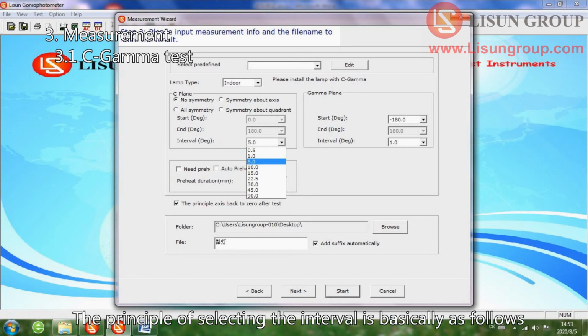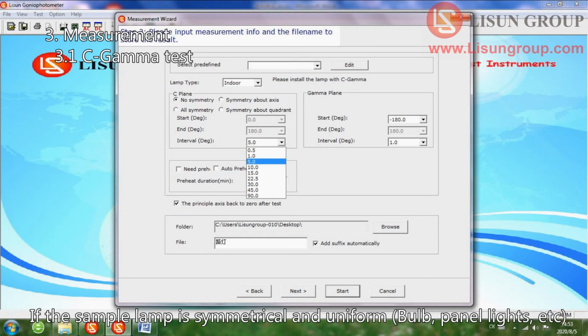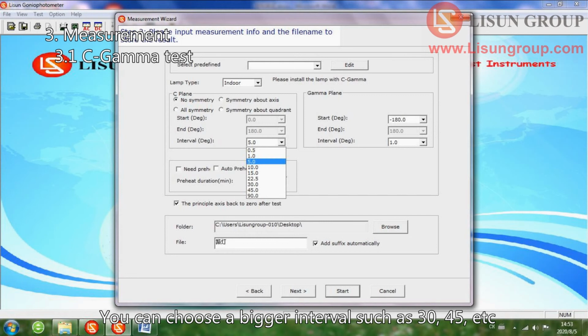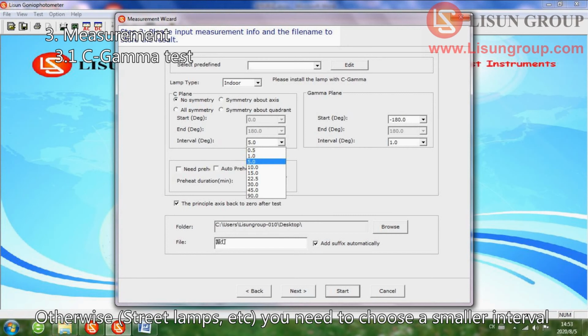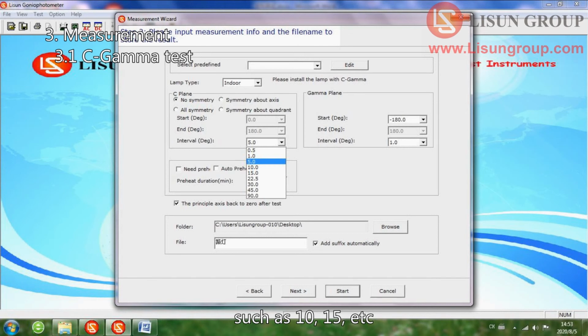The principle of selecting the interval is basically as follows. If the sample lamp is symmetrical and uniform, such as bulb, panel lights, etc., you can choose a bigger interval such as 30, 45, etc. Otherwise, for street lamps, etc., you need to choose a smaller interval, such as 10, 15, etc. Bigger interval needs less time to finish the test. Smaller interval needs more time to finish the test but the data is more accurate.